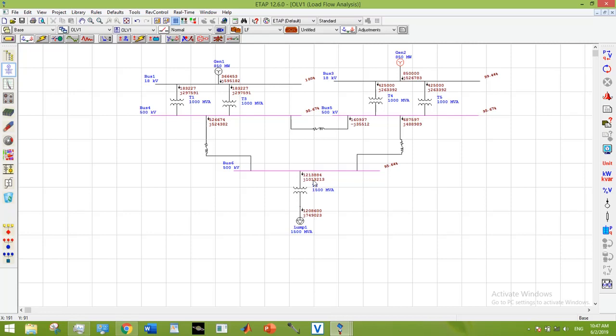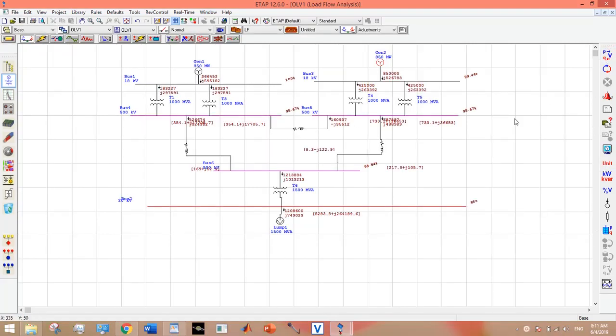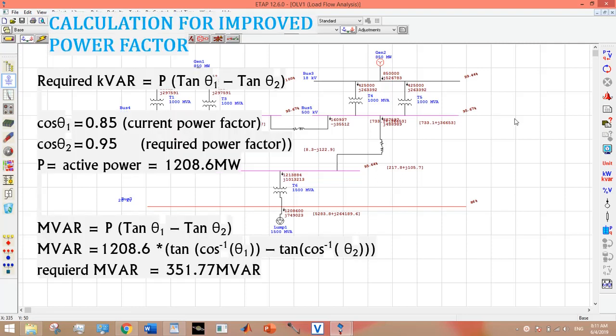Let's move towards other problems in our SLD. Now I am going to remove the overexcitation issue of Generator 2. The first method was to change the MVAR limits, which we have done with Generator 1. The other method is to improve power factor.